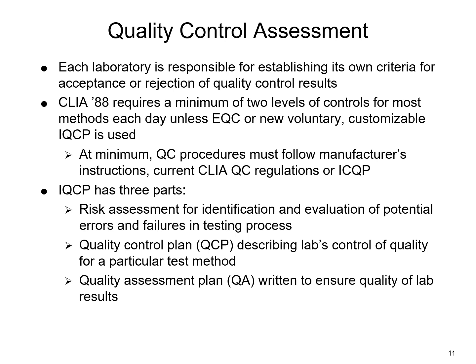You still have to establish that it is acceptable, that anytime it runs a test, there's a low risk of it actually sending out an invalid result. So you do these IQCP studies because the manufacturer says you only have to run QC for X amount of days or every 30 days. And so every 30 days your analyzer will alert you it's time to run QC again. So you have to have done the studies to say that this machine maintains its accuracy for that 30 days.